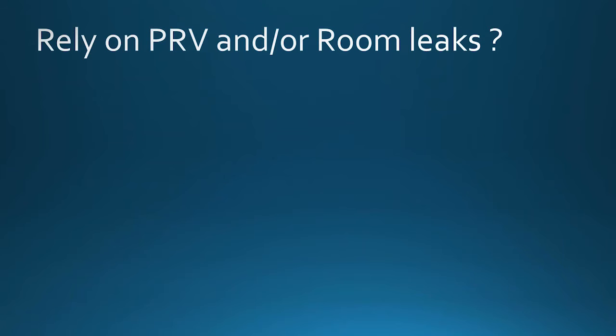And in the U.S., we often rely on room leaks. There's a different philosophy in Europe where they don't rely on room leaks at all, and they will always install a PRV to relieve the pressure, regardless of whether the room leaks or not. We are finding, however, that in a lot of cases, when we do the peak pressure evaluation, we do need to install a PRV.